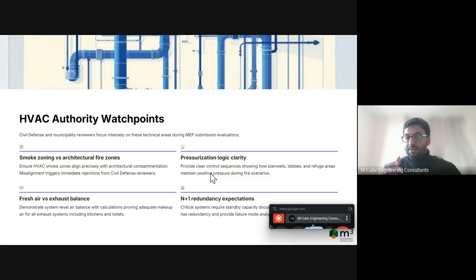The pressurization logic and clarity of sequence should be clarified in terms of stairwells, lobbies, and refuge areas. Generally, in a fire scenario, you need to ensure how the pressure logic happens in terms of fire strategy. This is also being asked now for high-rise and super high-rise buildings, so you need to ensure this logic is presented.